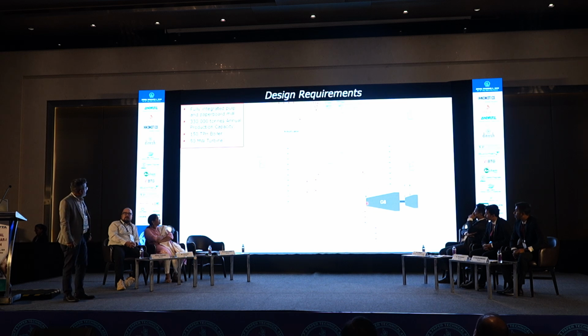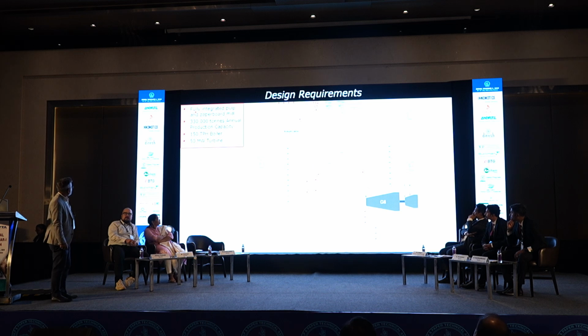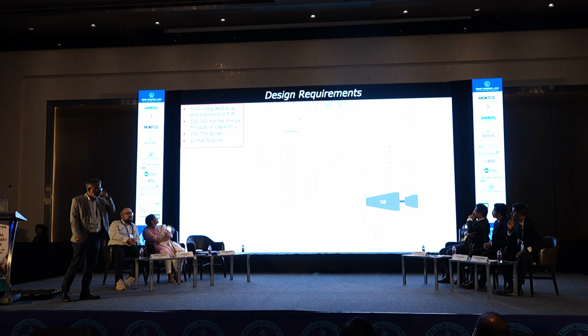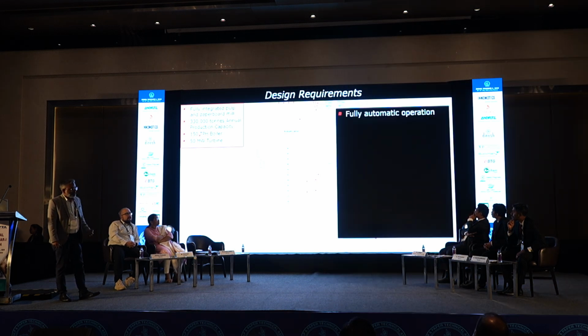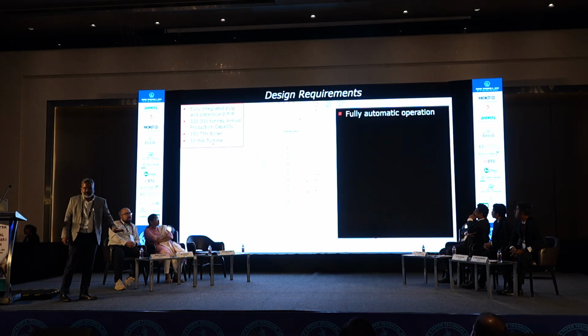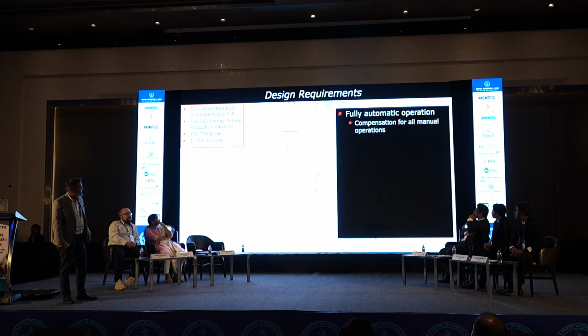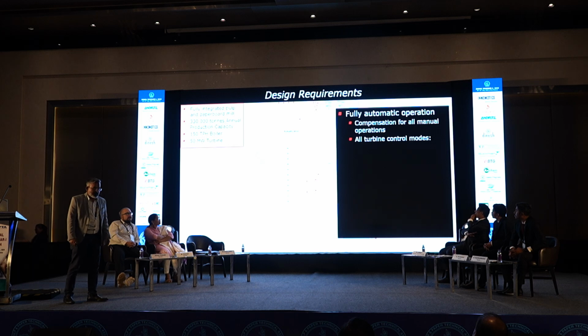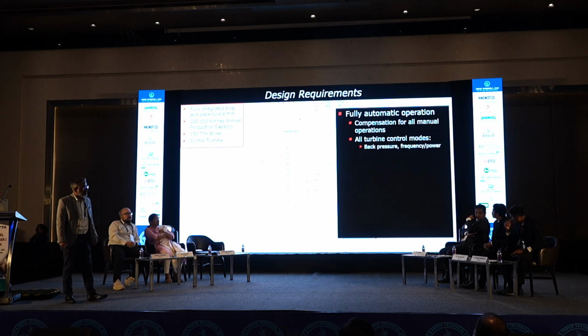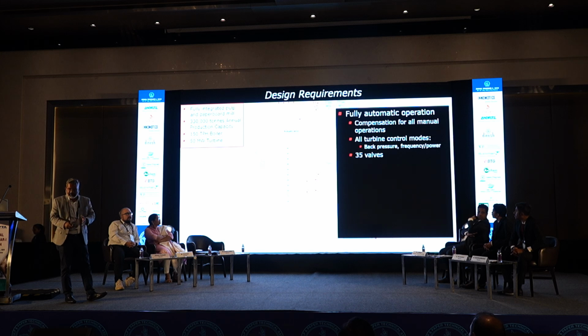So for this particular case, it's a fully integrated pulp and paper mill, around 330 tons of capacity, with a 150 TPH boiler and a 50 megawatt turbine. This was their design requirement: they wanted to run their plant in completely auto mode, compensating for all manual operations. For all turbine control modes like back pressure, frequency or power, there were 35 valves along with the PRDS system and a steam accumulator in the system.